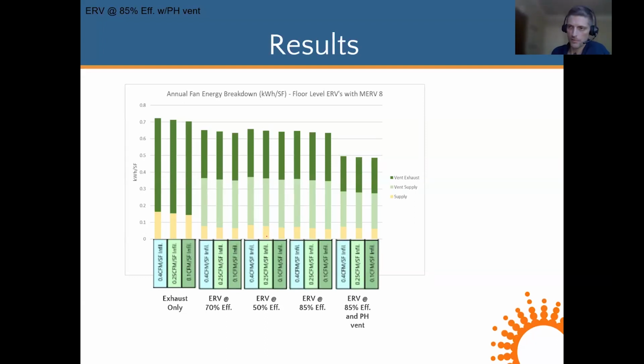But because of the heat recovery, the conditioning air fan power is lower. So the total fan power ends up still being lower for the ERVs over exhaust only. There's also no significant increase in fan power with increasing effectiveness of ERVs. So there's no increase in operational costs with different ERV effectiveness, telling us the main hindrance to high performance ERVs is just the first cost. We also see the effect of reducing the ventilation flows. That is obviously going to be our biggest energy saver.